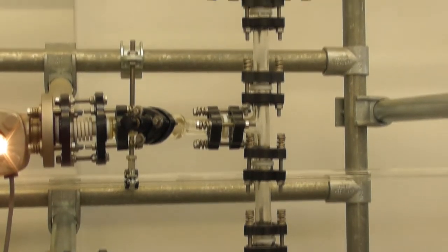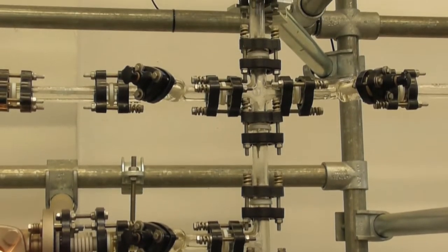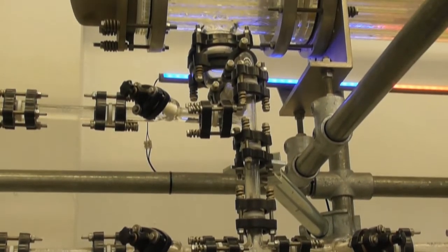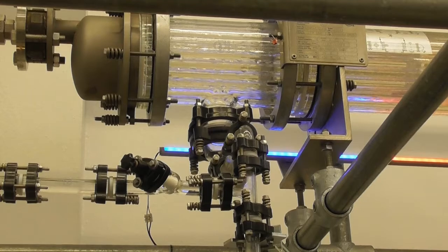Banking up of condensate would lead to heavy problems like bad product quality or water hammer in the heat exchanger, which could harm the vessel or destroy the internal parts of the heat exchanger.